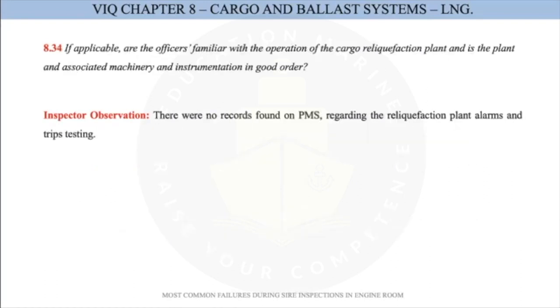Next one, if applicable: are the officers familiar with the operation of the cargo reliquefaction plant, and is the plant and associated machinery and instrumentation in good order? So the reliq plant, that is the reliquefaction system, a huge system which is used on Q-Flex and Q-Max vessels. And the observation: there were no records from the PMS regarding the reliq plant alarms and trip testing.